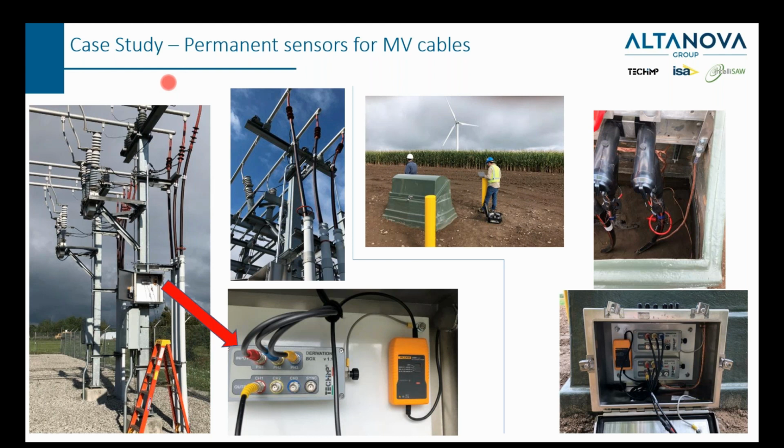Technically, they can do the test anytime when they feel it's necessary, or they can set up a testing plan. For example, if they want to test every month or every 2 months, they can build up solid trending data for that circuit. And once there's any change in the circuit, it should be very effective to show in the trending analysis.